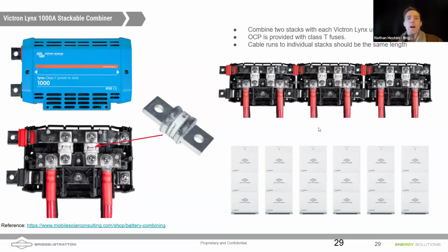Why would we want to do that, Nathan? During high power outputs, you can lose a little bit of voltage on lines, and the longer the line, the more voltage you lose. So when you're rapidly discharging or rapidly charging, these small imbalances in the voltage a battery sees at its terminals can result in less power output or input from that individual battery. To properly balance the load across the batteries, we need to use cables of equal length. If you don't, you'll shorten the lifetime of the batteries with the shorter cables, and overall degrade the aging of your system.